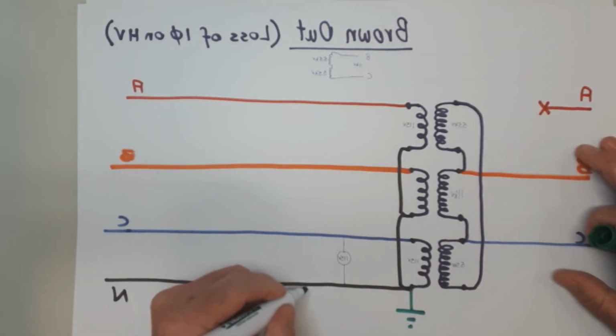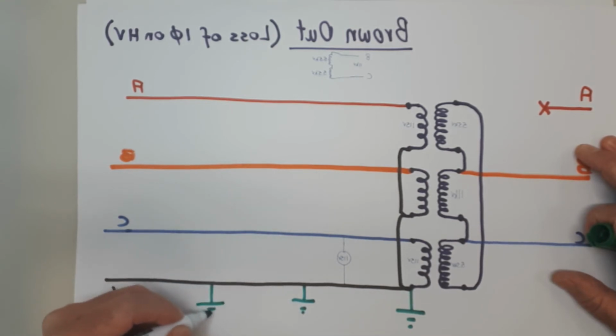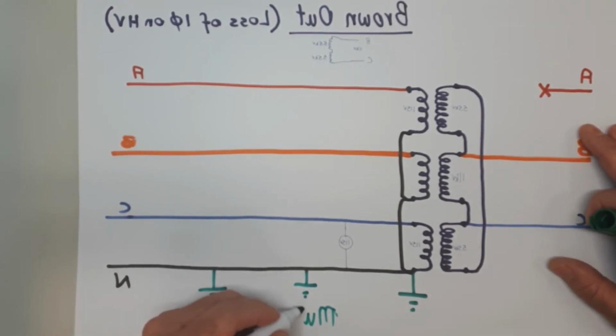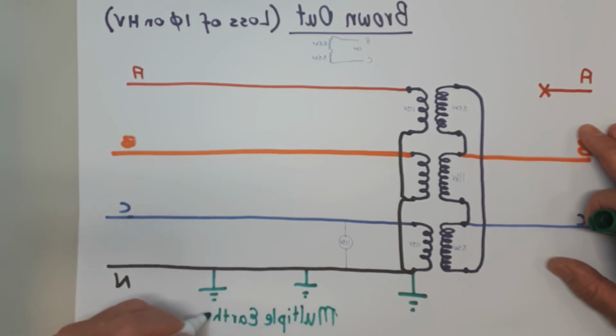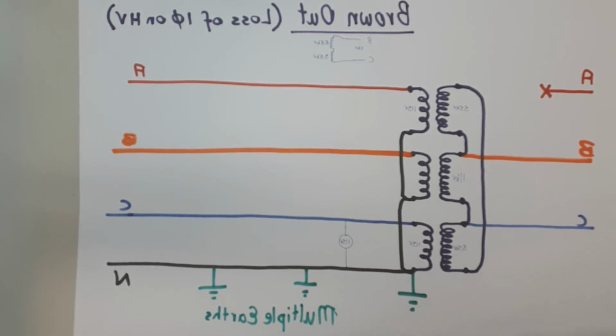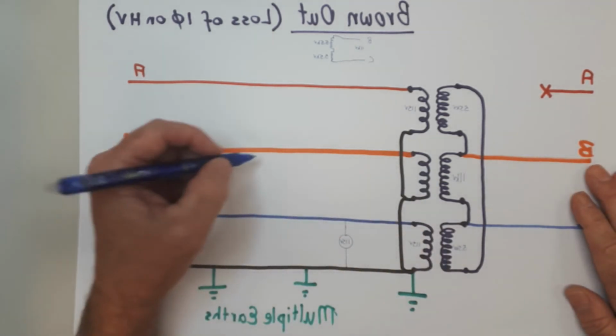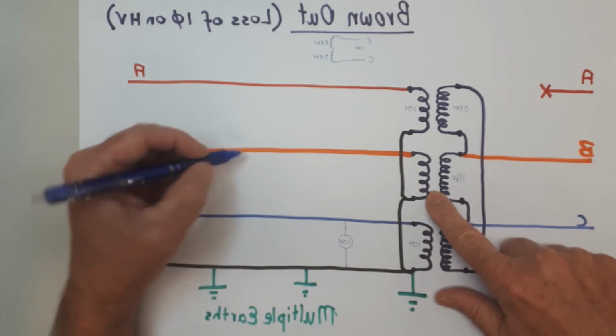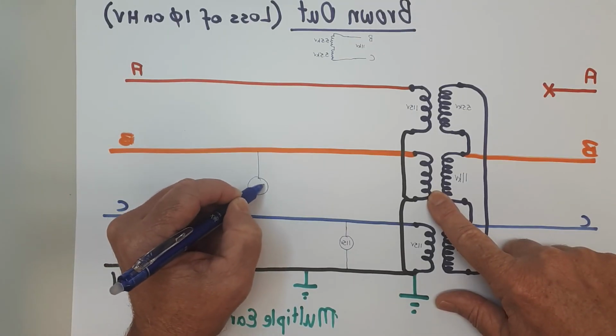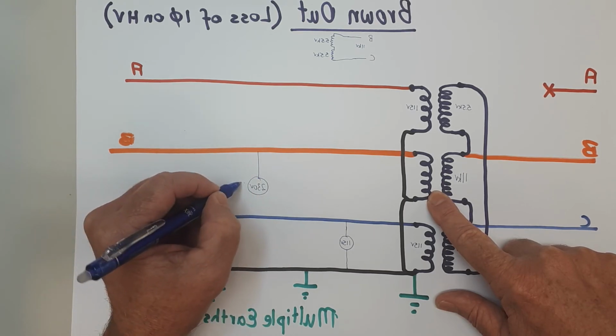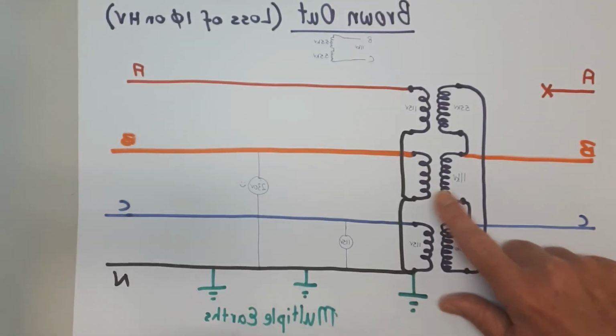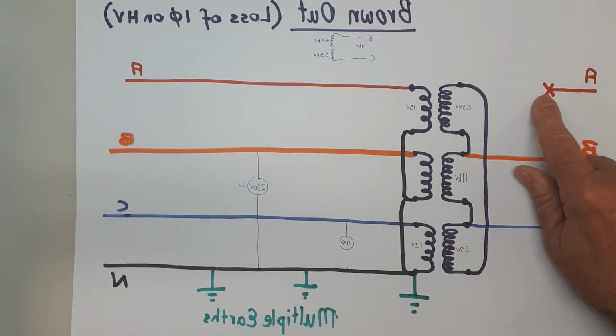What I should have put in is a few more earths here, because as we know, there are multiple earths. I'm running out of space there. There are multiple earths on that neutral. They're all over the place. You see them everywhere. And there's one at your switchboard too, hopefully. All right, and so if you're on B phase, you're still getting the full voltage energizing the winding you're on, so you're okay. You're going to get 230 volts. You don't even know that there's been a loss of a phase here.